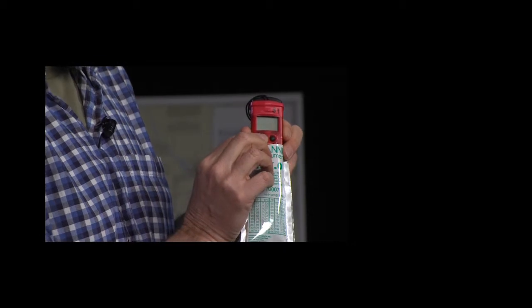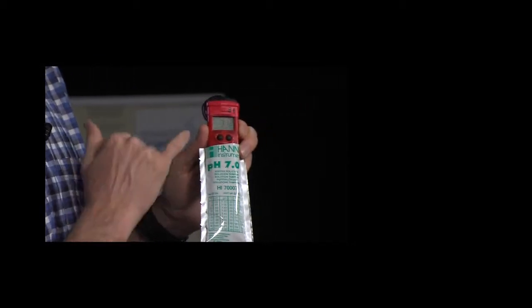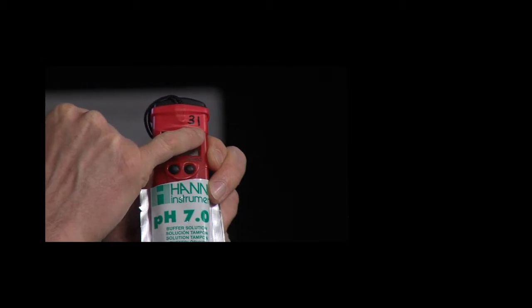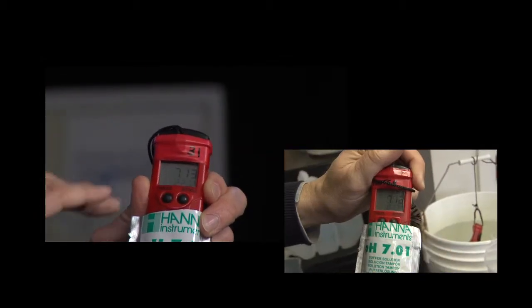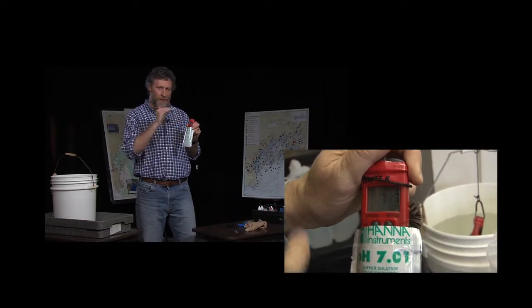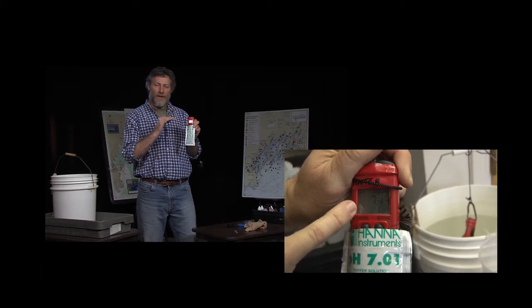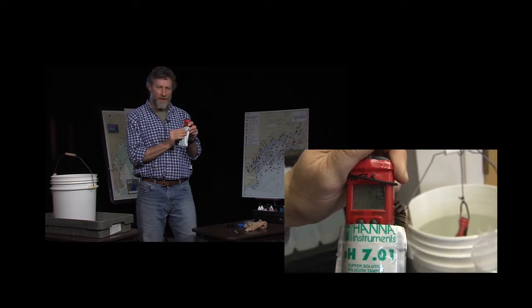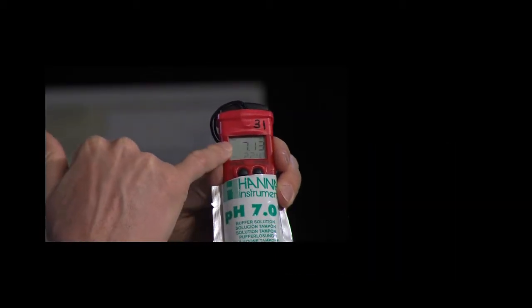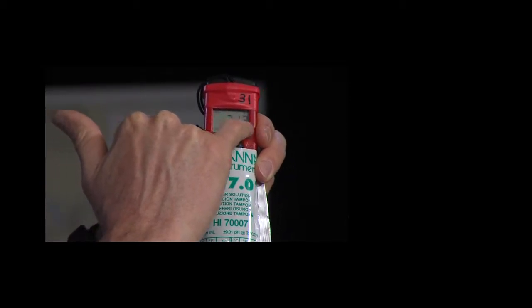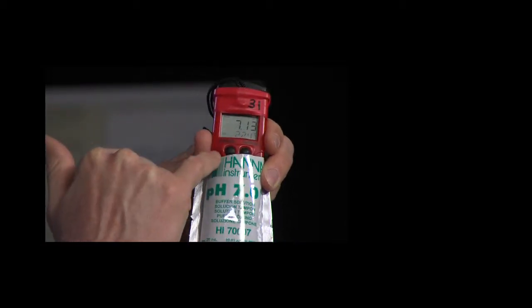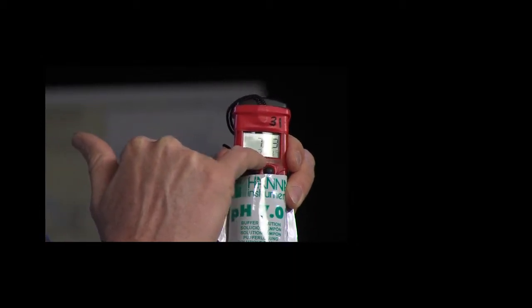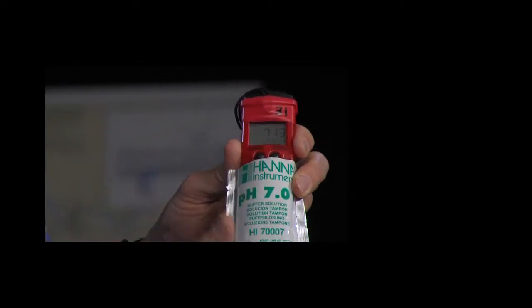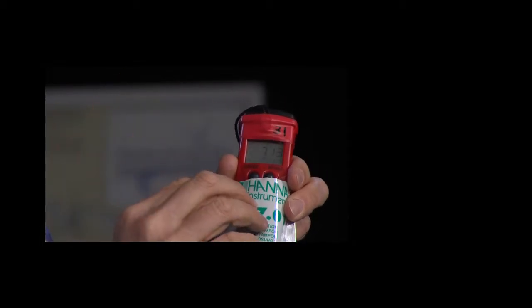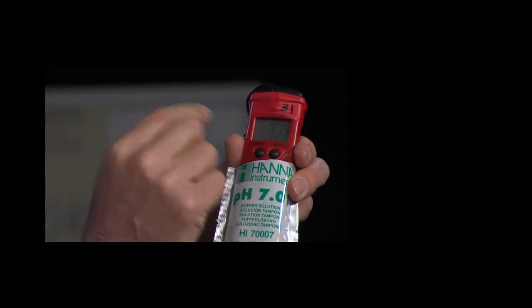So we'll push the little black button on, and it will read battery first. Typically it's around 100%. These are new pH meters that have new batteries. It's something we'll also want to keep an eye on. If the battery percentage goes down lower than 60%, then we know that it's time to change the batteries. Then it will start to give you a number up here that is a pH number, and underneath it is the temperature of the water or the temperature of the sample in here. We're not too concerned with the temperature of the sample right now. We're just going to calibrate it.